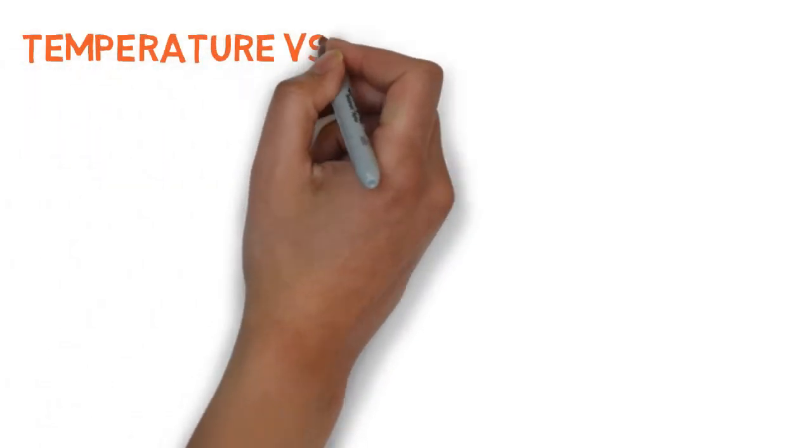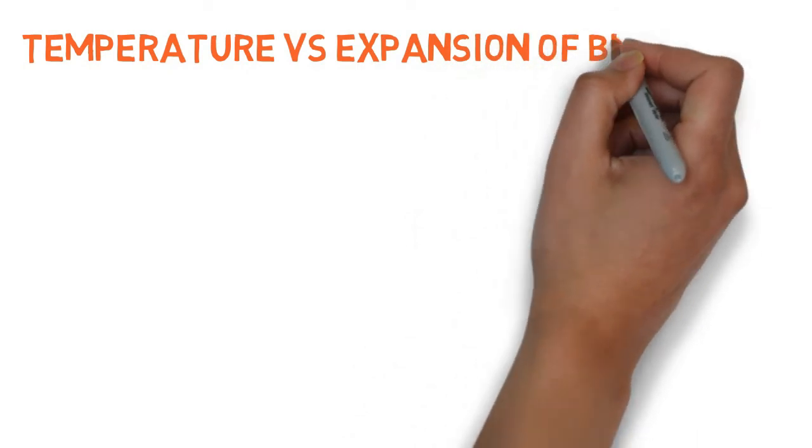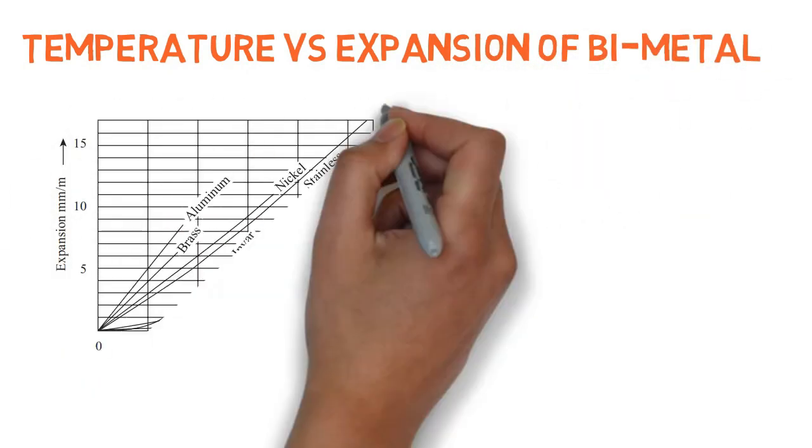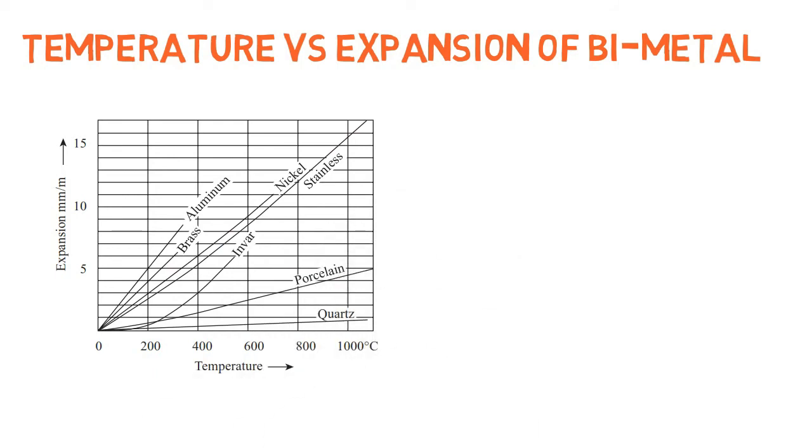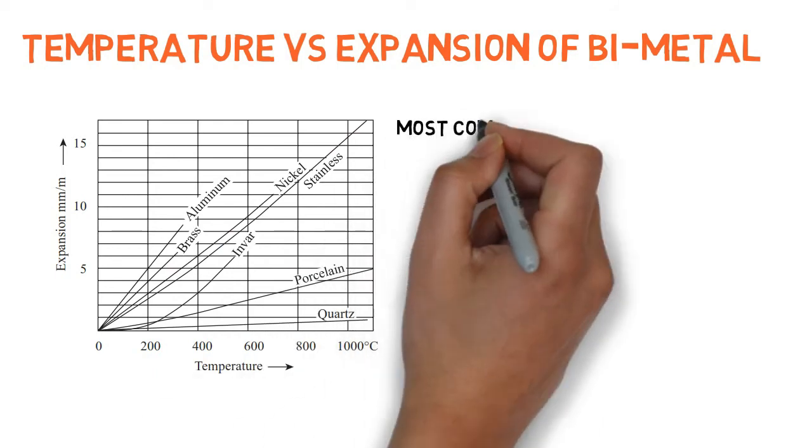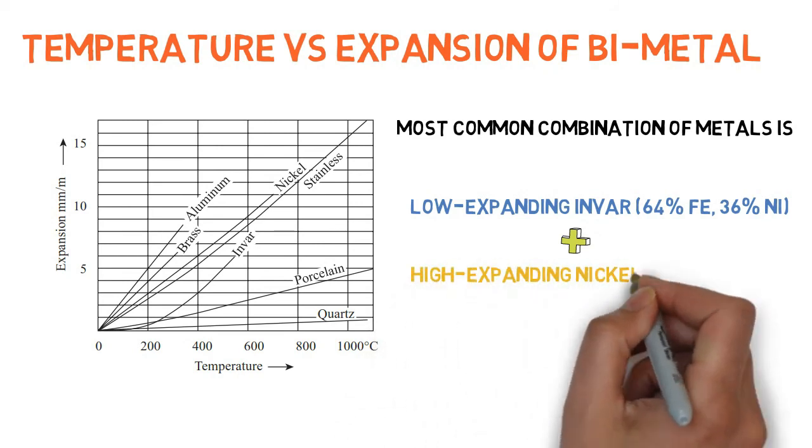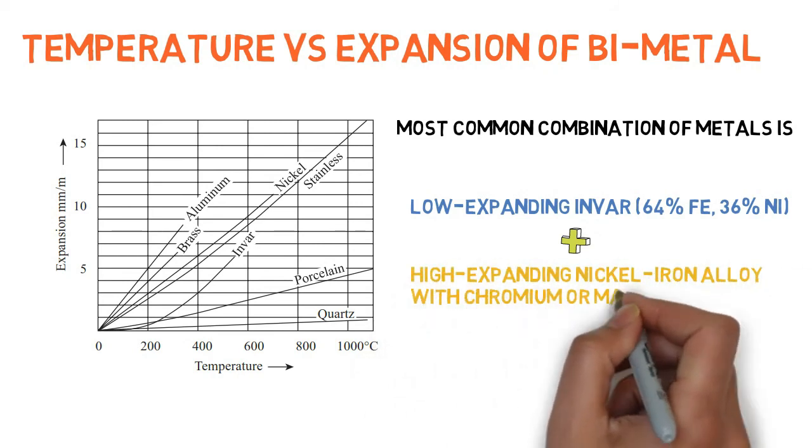Temperature versus expansion of various bi-metals can be seen in the graph below. The most common combination of metals is low expanding Invar and high expanding nickel iron alloy with chromium or manganese added.